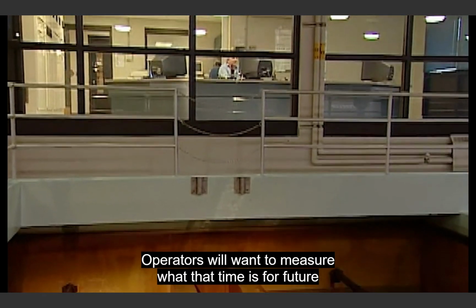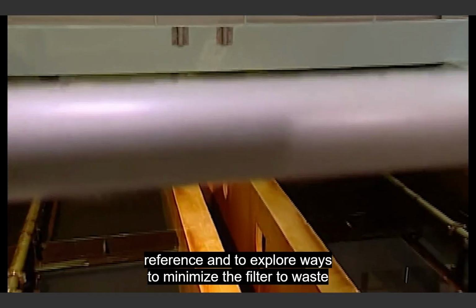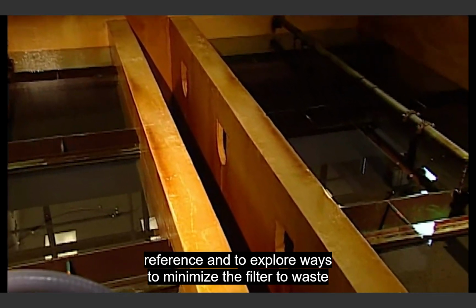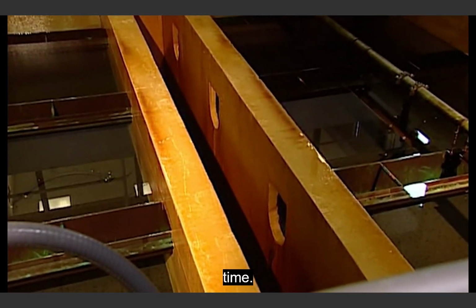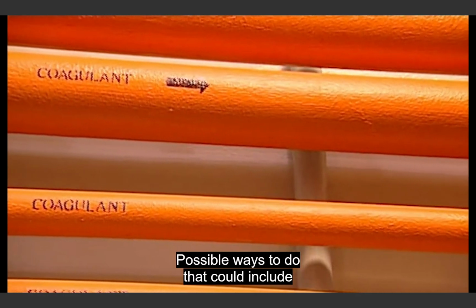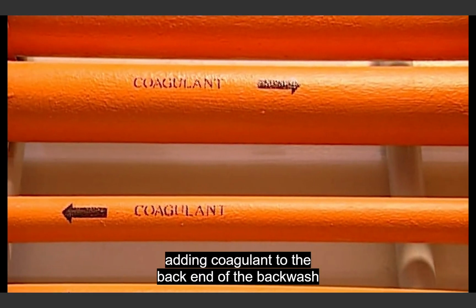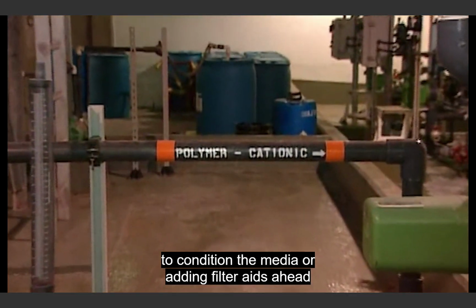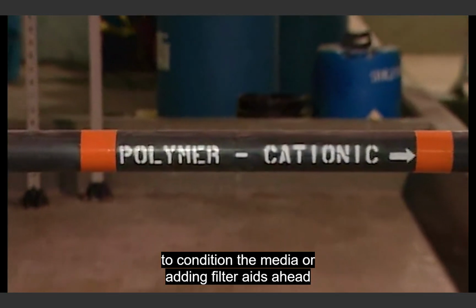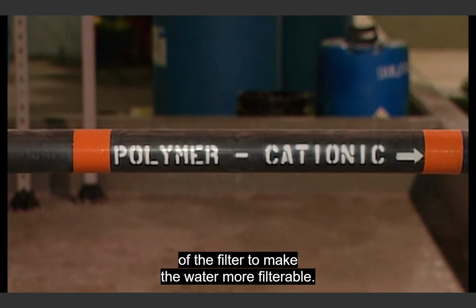Operators will want to measure what that time is for future reference and to explore ways to minimize the filter-to-waste time. Possible ways to do that could include adding coagulant to the back end of the backwash to condition the media, or adding filter aids ahead of the filter to make the water more filterable.